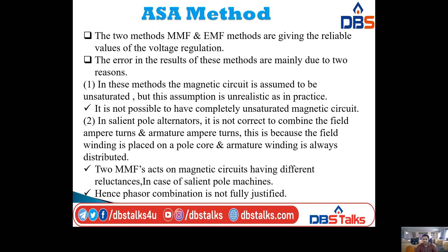The MMF and EMF methods give reliable values of voltage regulation, but there are errors in the results mainly due to two reasons. The first reason is that in these methods the magnetic circuit is assumed to be unsaturated, but this assumption is unrealistic in practice as it is not possible to have a completely unsaturated magnetic circuit.